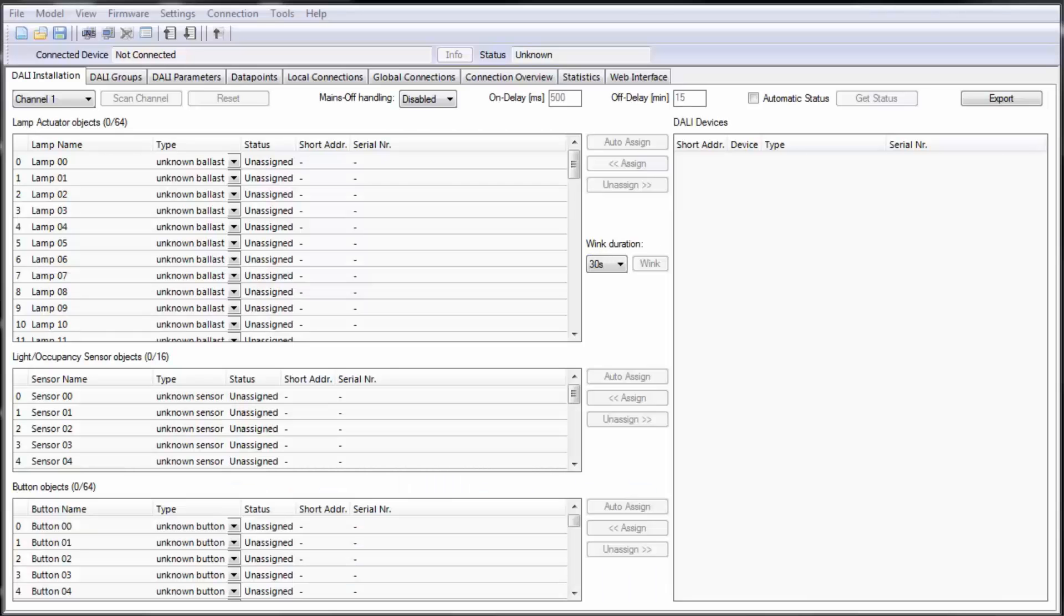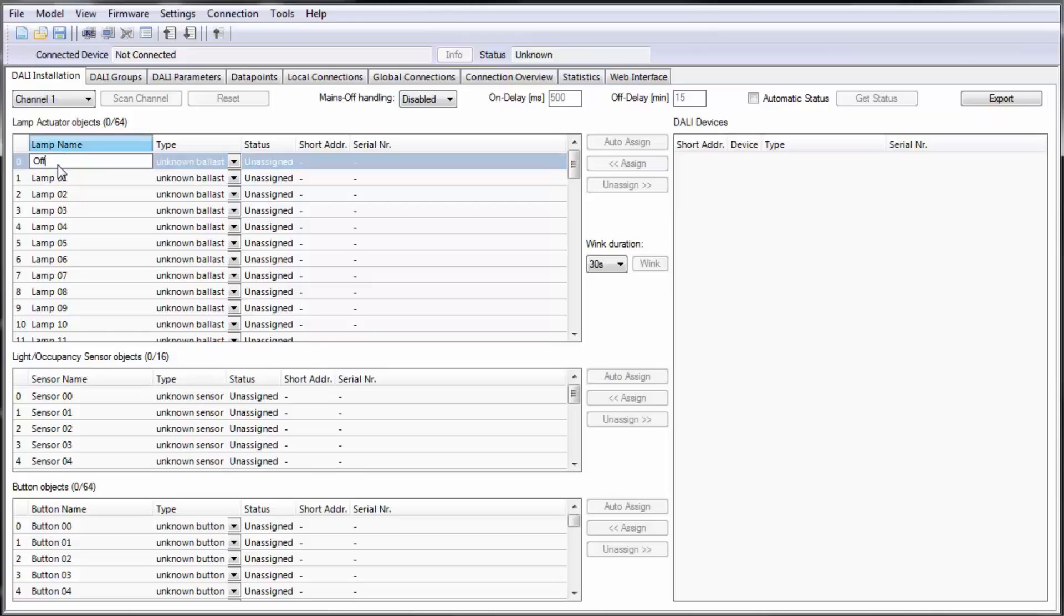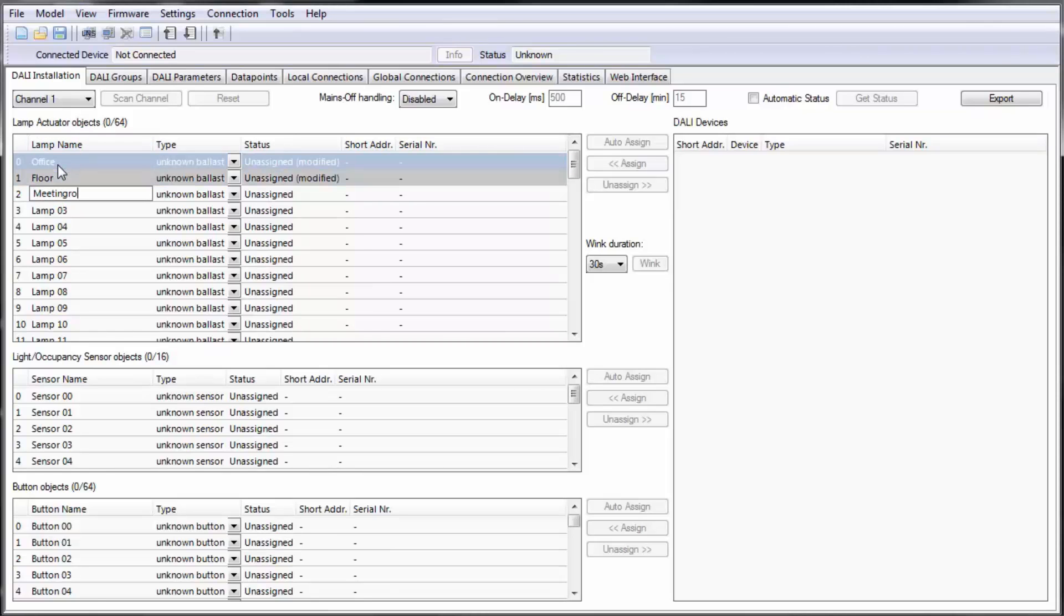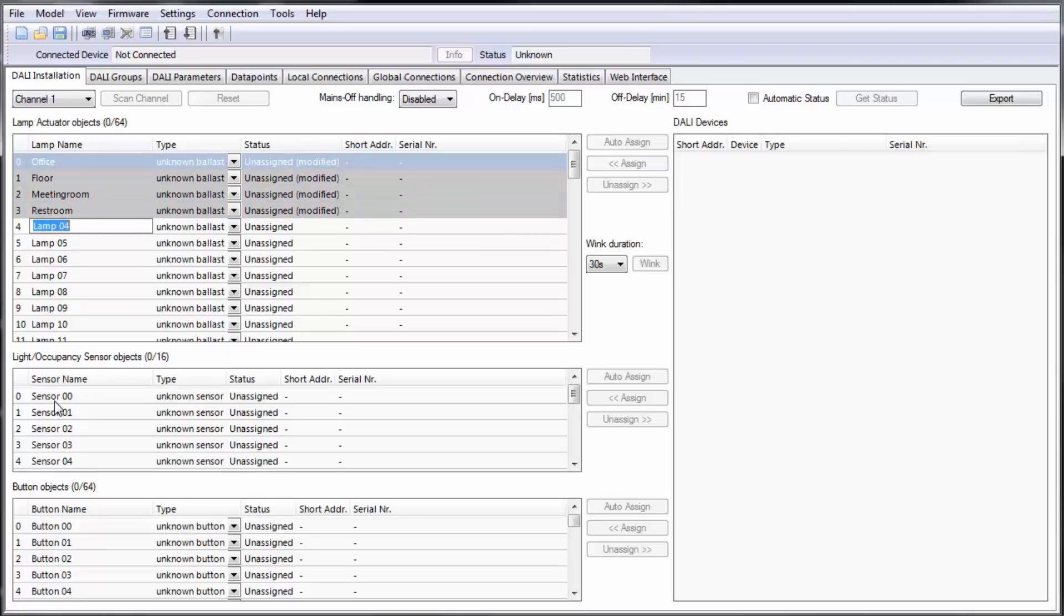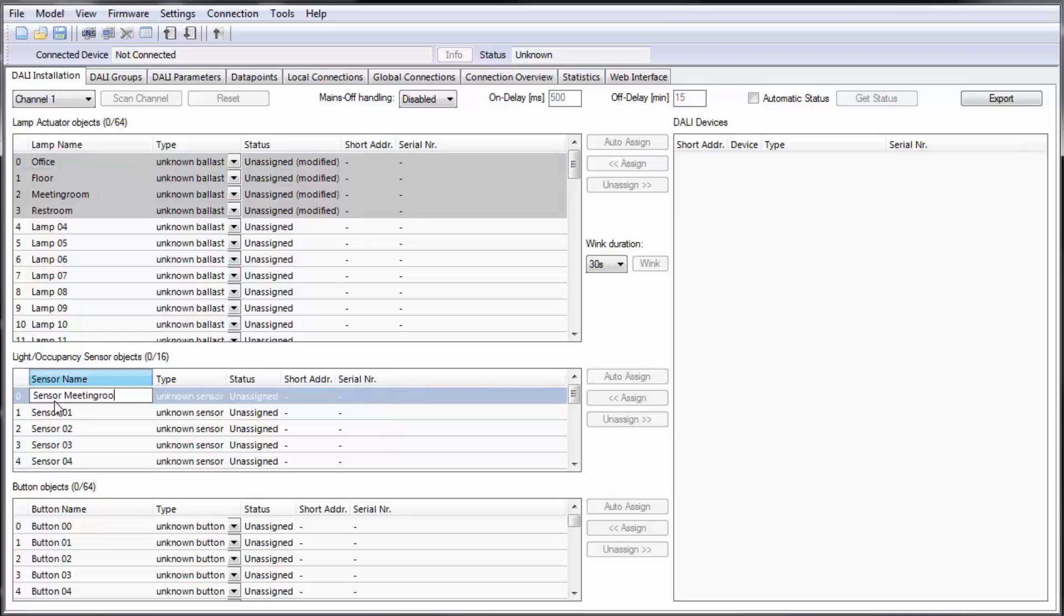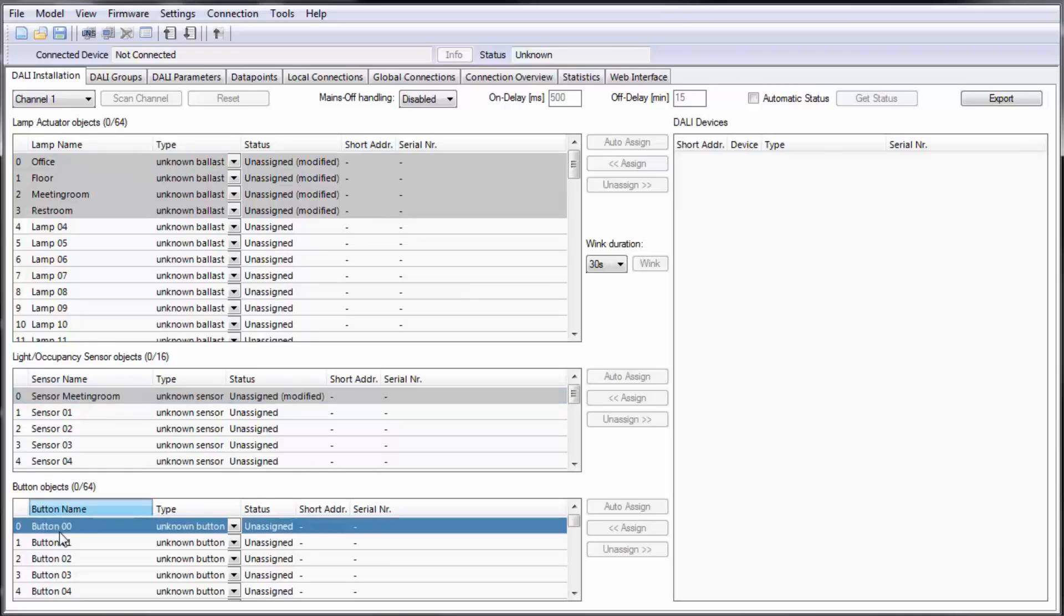The DALI wizard allows to identify DALI devices by using a binary search method. Therefore it is required to have already set names for the DALI devices. The names can be adapted in the web interface or like in this video by using the configurator.